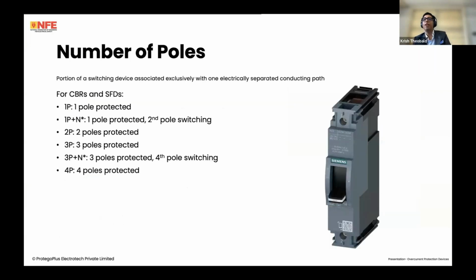When it comes to the number of poles, for circuit breakers and switch fuse disconnectors, that's what SFD denotes. The basic way it works is that the pole is a portion of a switching device associated exclusively with one electrically conductive path. So I think it really requires no introduction. That was just nomenclature. Basically, you have the one pole circuit breaker, which is this. This is the one pole MCCB, by the way.